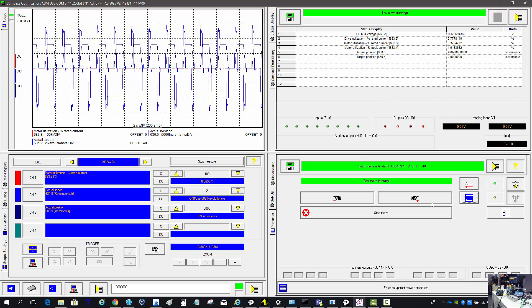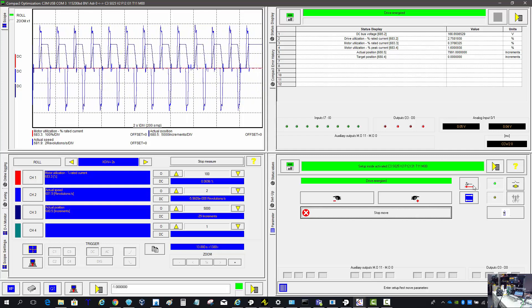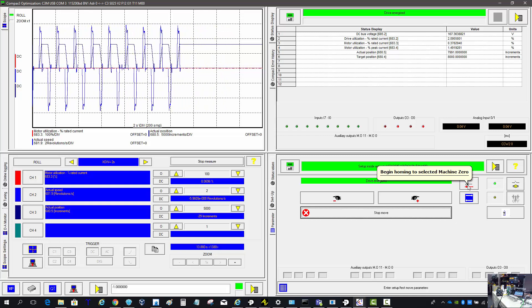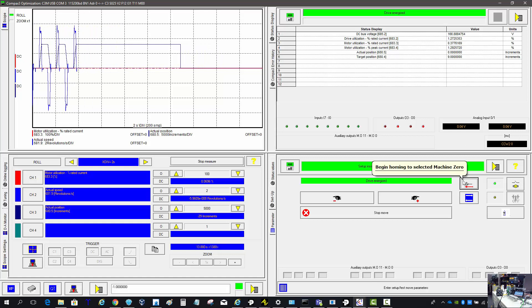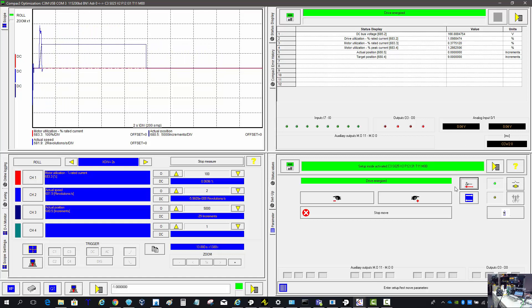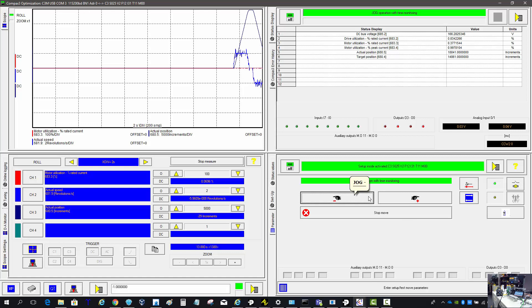The actual position is displayed here. If I stop the move I'm very close to 8,000 counts. When I click 'Begin Machine Home Zero,' it doesn't actually physically move the motor but it resets the actual position — that's home mode 35. If you're homing to a home switch based on the drive configuration, clicking this will begin the homing move and once the switch is found it should reset to zero. That's how you set that up for a linear actuator. You can also hold the jog buttons to move back and forth.